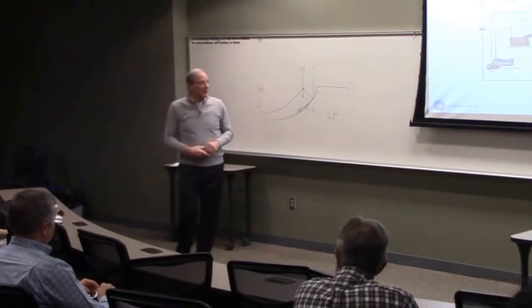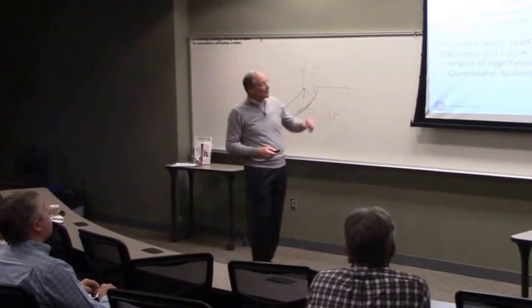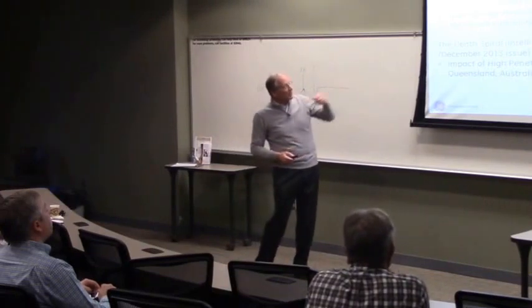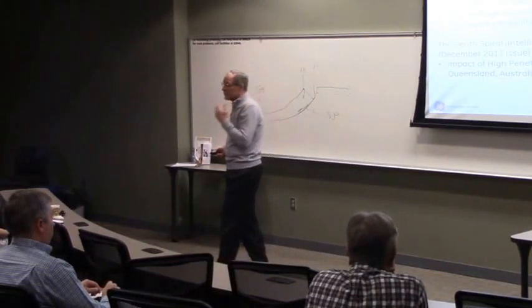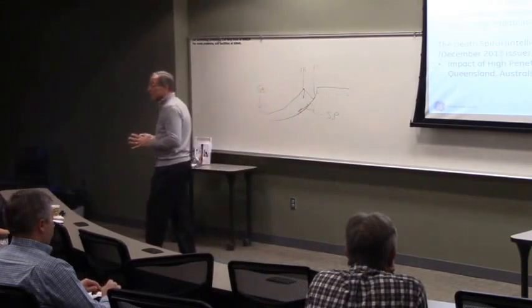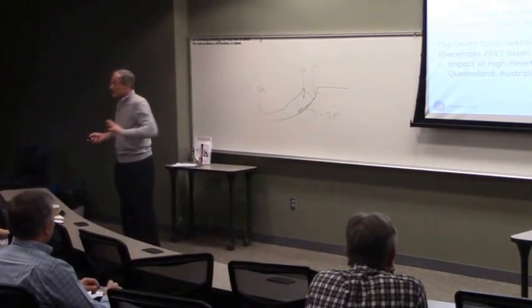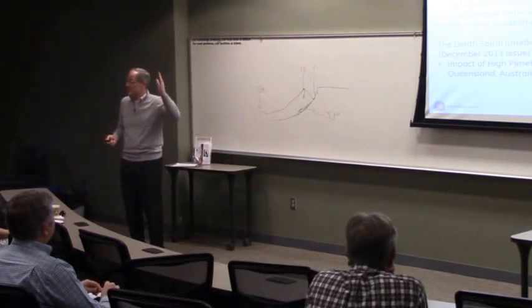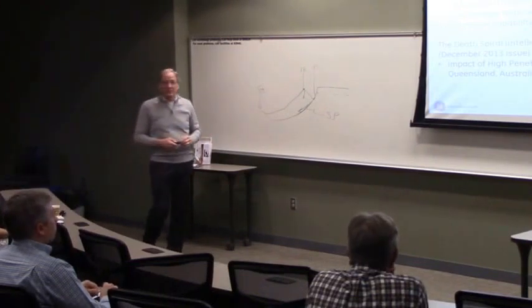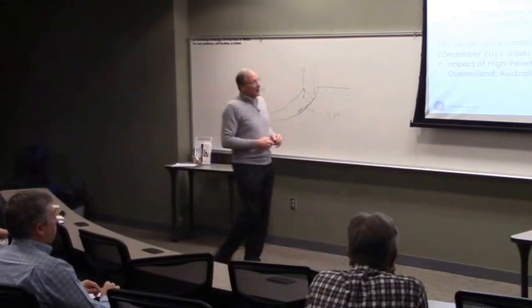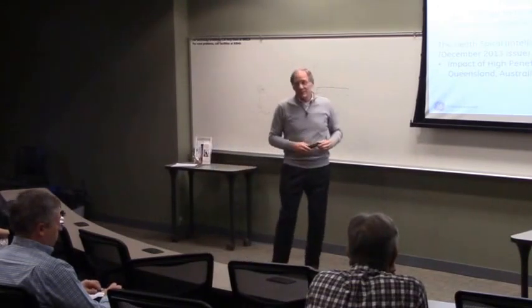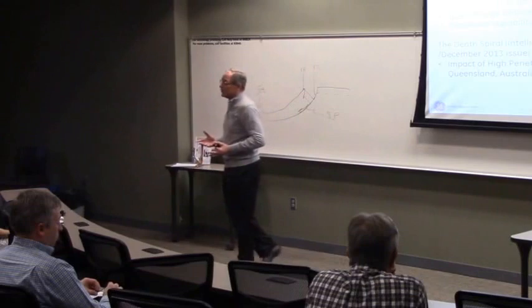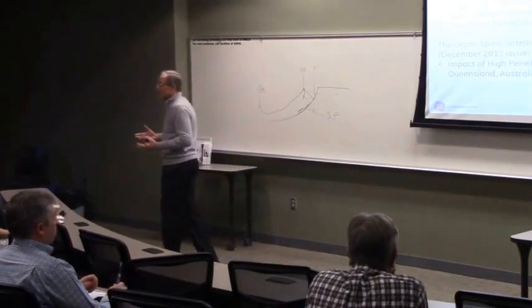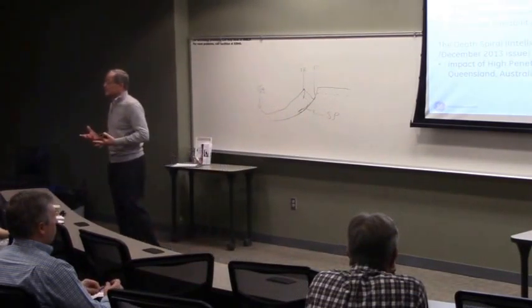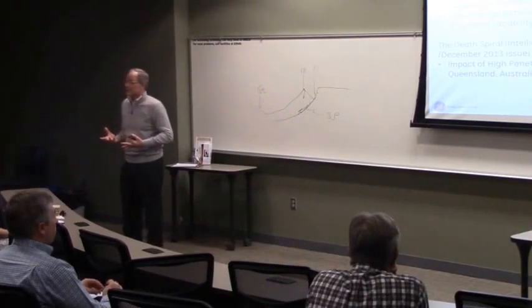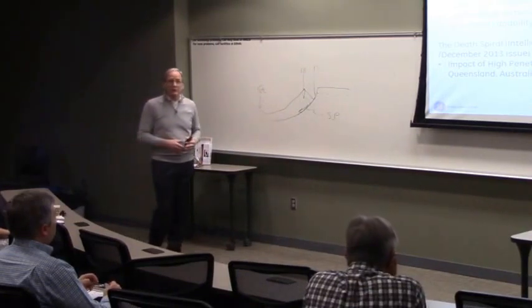So I'll go back to here. In Power Electronics magazine I wrote an article, and I worked with San Diego Gas and Electric to have voltage waveforms from this feeder in the article. You should see the spikes and the oscillations of the voltage on this feeder. The premise of the article was that mechanical means of control, with a future grid with high penetration of renewables, just doesn't make sense because of the volatility. Mechanical means of control will just wear out too quickly.